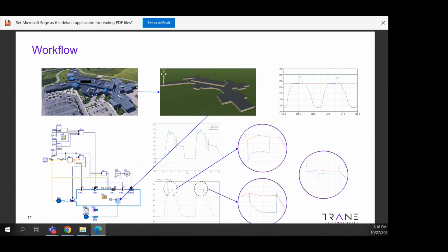Here we can see that with one of the strategies, there is a sudden, as expected, drop in the demand. So this is fine. But with the other strategy, the demand drops slowly. So that strategy may not be that useful, or you have to start a little bit ahead of time when the request to reduce demand comes.